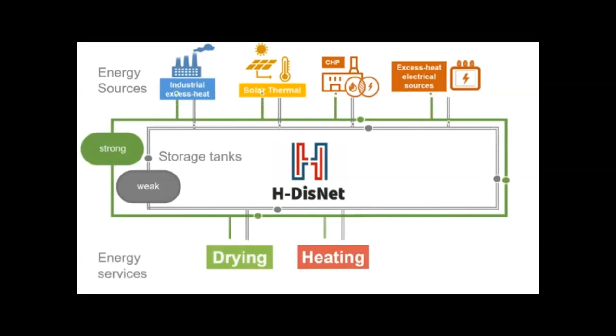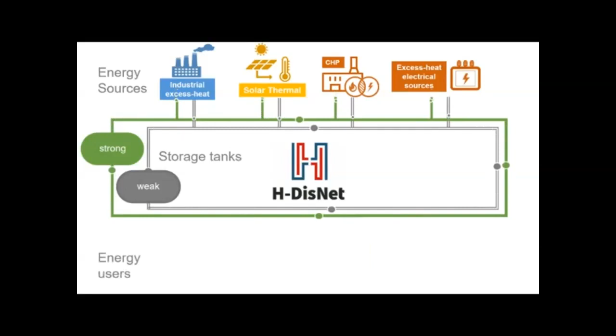The strong liquid desiccant mixture can then be pumped to energy users for air drying, heating, or cooling services. The dehumidification of air to facilitate industrial drying is the simplest application. Here, the strong desiccant water mixture is used together with a dehumidifier unit to dry air for a local indoor swimming pool. The combination of dry air and an evaporative cooler can be used to support air conditioning for the cooling of local buildings and greenhouses.